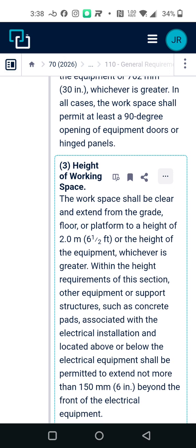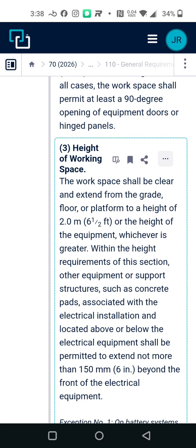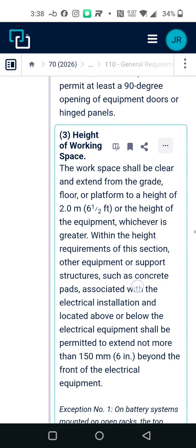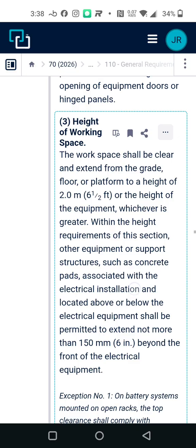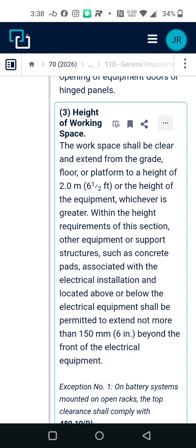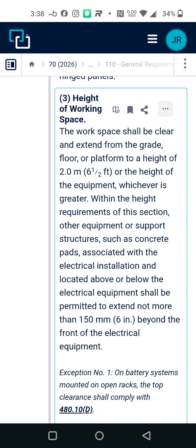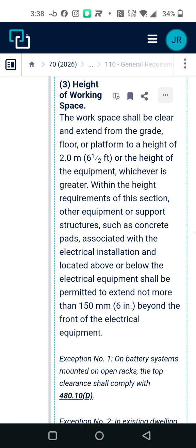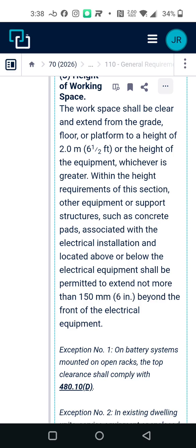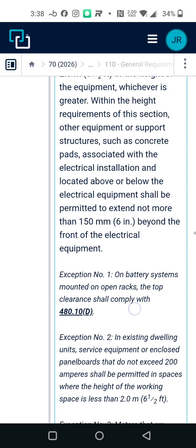Height of working space. The workspace should be clear and extend from the grade, floor, or platform to a height of 2 meters, or the height of the equipment, whichever is greater. Within the height requirements of the section, the equipment or support structures, such as concrete pads associated with the electrical installation and located above or below the electrical equipment, should be permitted to extend not more than 150 millimeters beyond the front of the electrical equipment.